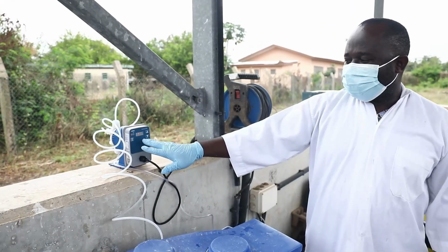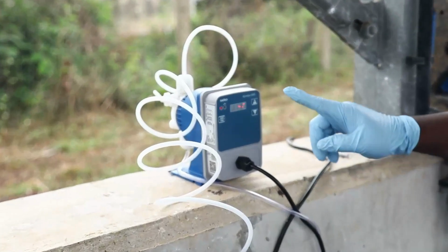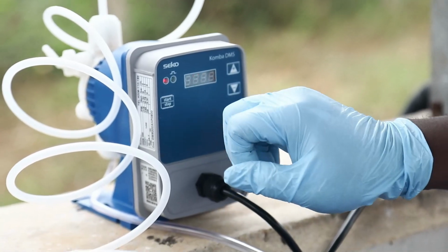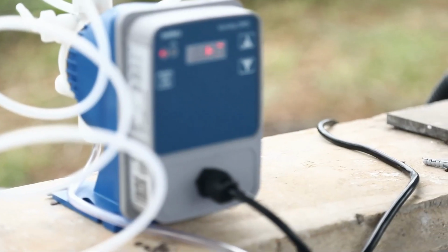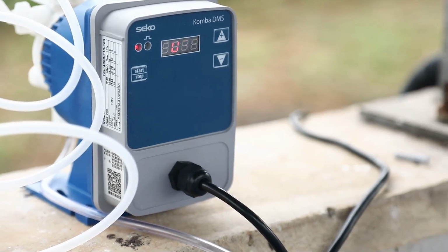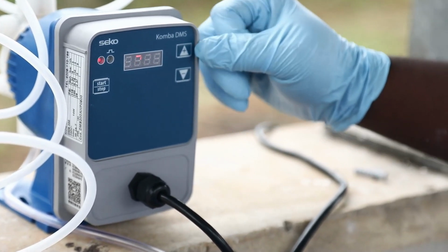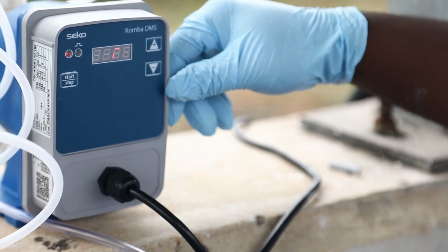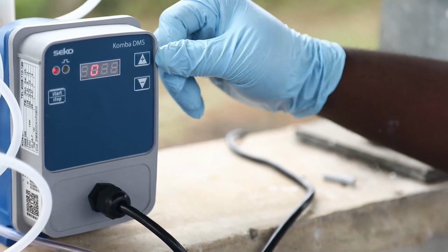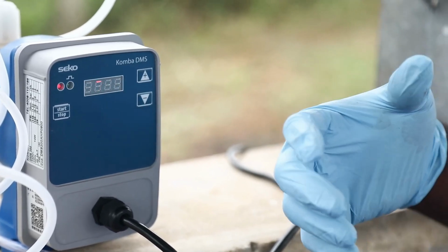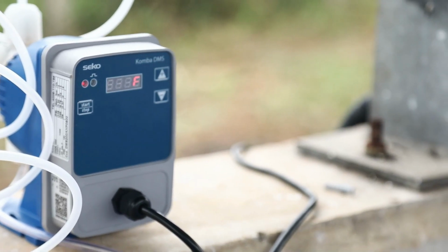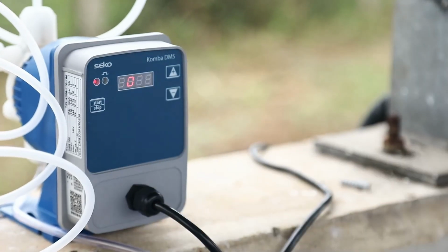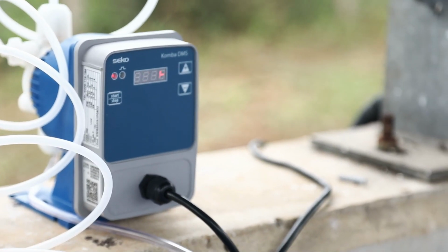So as you can see, it's at the off position. We have 3 knobs here. This knob, which they've indicated start and stop, is what you use to put the machine on and then put the machine off. Okay, and then we have 2 knobs on the side here. There's a plus on one and a minus on the other one. These 2 knobs regulate the pulse, as in the rate at which you want the doser to put the stock solution into the treated lines. Okay, so basically these are just 3 knobs that you have to be conversant with.